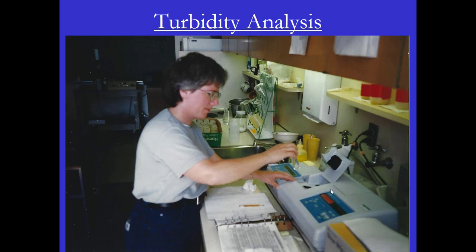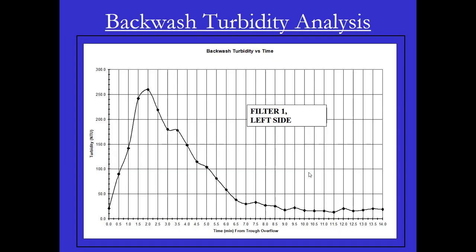After samples are collected, you want to take them to the laboratory, run them for turbidity, and then graph that data. You can see when the backwash started, after a minute or two the turbidity went up to about 250, which is good, and then it gradually came down. At about seven to seven-and-a-half minutes the turbidity is maybe 40, and at nine minutes maybe 20. From nine to about 14 minutes, the turbidity stays about 20. This is an indication that you're washing way too long.